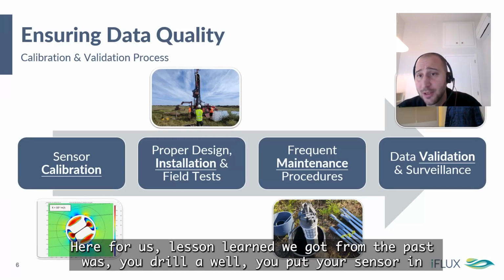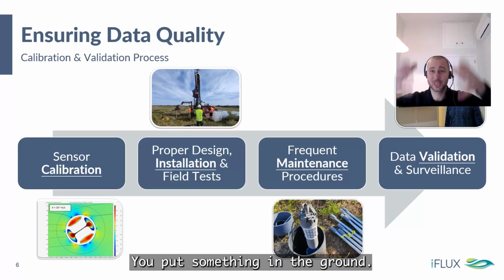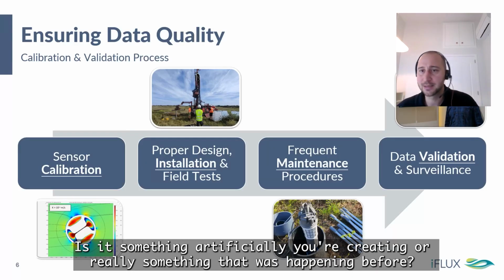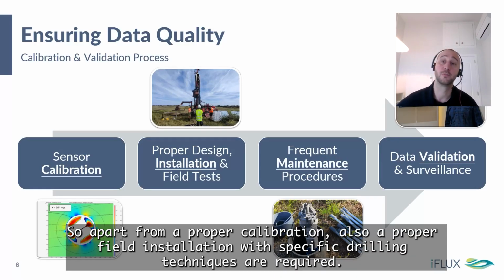Here, the lesson learned we got from the past was: okay, you drill a well, you put your sensor in, nice, you measure something, you put something in the ground. So are you measuring what was there, or are you measuring flow which bounces off or gets extracted, pulled into your sensor? Is it something artificial you're creating, or really something that was happening before? So apart from a proper calibration, a proper field installation with specific drilling techniques is also required.